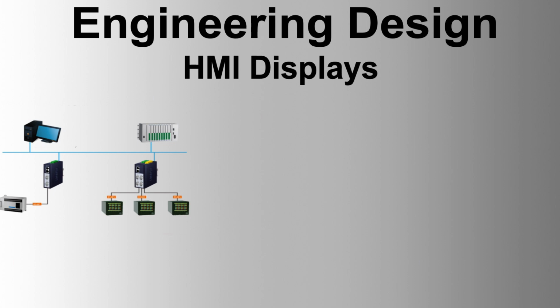Targets. Targets are areas within a graphic display that can be configured to call up displays, windows, faceplates, and initiate sequences or application programs. They have the same functionality as function keys, but are configurable for every graphic display. To ensure ease of operation, the target area should be at least 2 centimeters on touch targets. Smaller targets may be considered where trackball or mouse pointing devices are used. Generic targets should be considered for navigation purposes and consistently positioned in the screen. These may include calling detailed displays, help windows, toggling control lines, trend displays, etc.